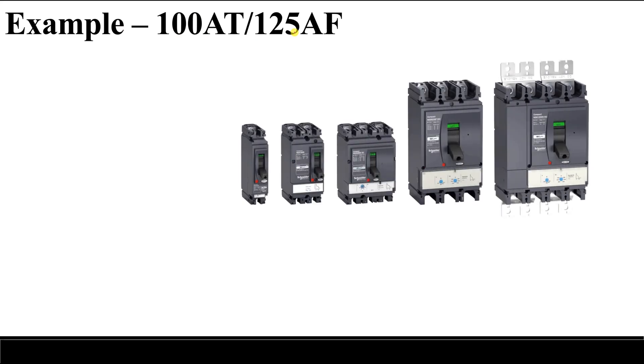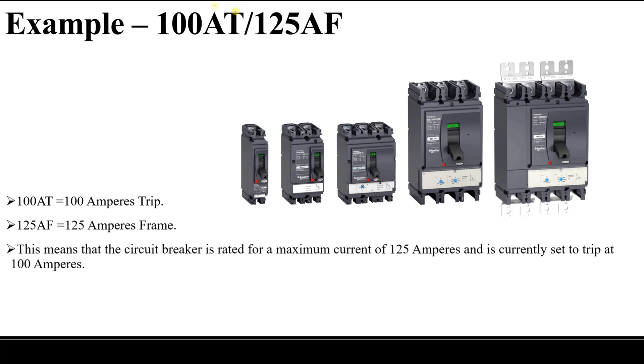For example, if we have a circuit breaker of 100AT and 125AF, it means this circuit breaker will trip at 100 amperes. We are selecting it to trip at 100 amperes, and the 125 represents the maximum current that the circuit breaker is designed to trip at. So the maximum rating for the circuit breaker is 125 amperes, and it is currently set to trip at 100 amperes — because the ampere trip is set at 100.